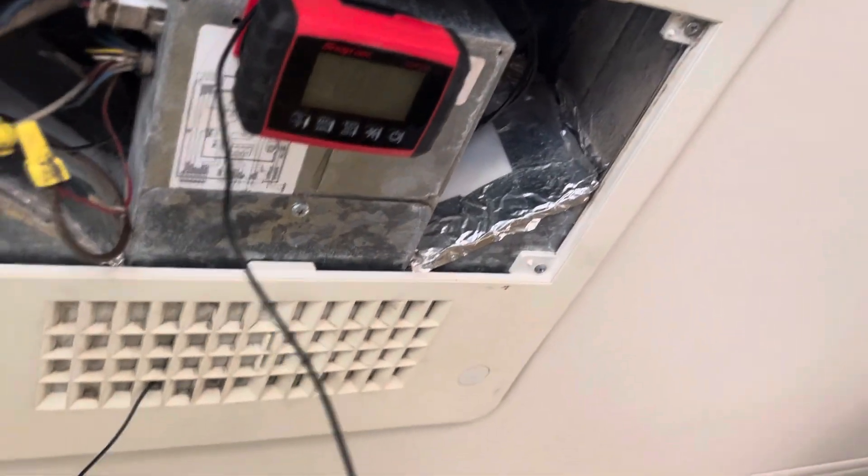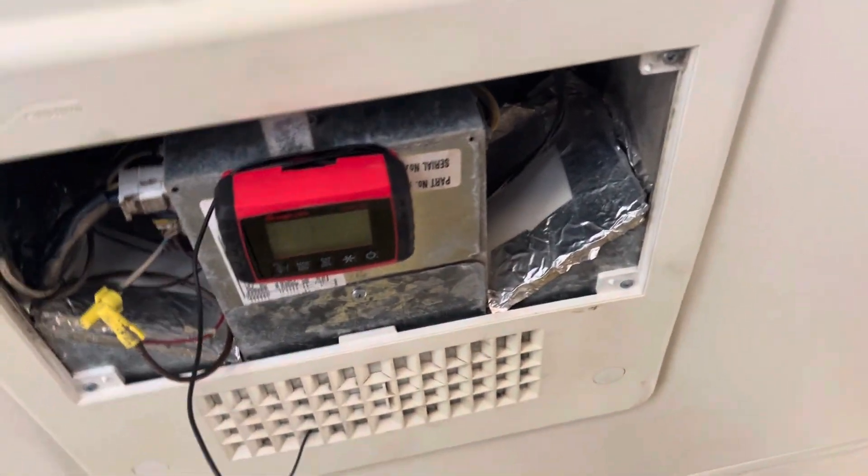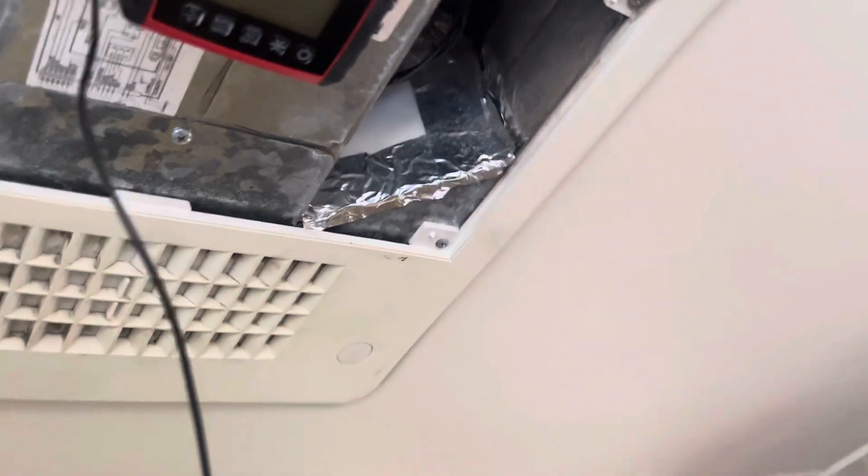So the air conditioner wasn't performing very well, and that's why we're doing the service on it. The coils on this one were some of the dirtiest I've ever seen. I had to literally clean it like four times using a combination of foam and Coil Brite and a vacuum.